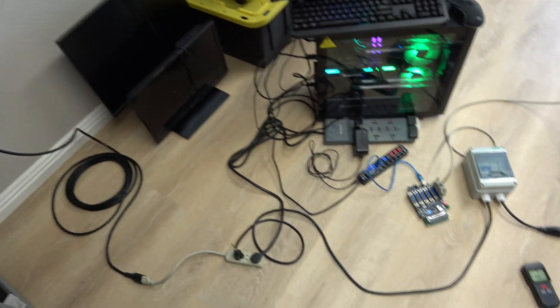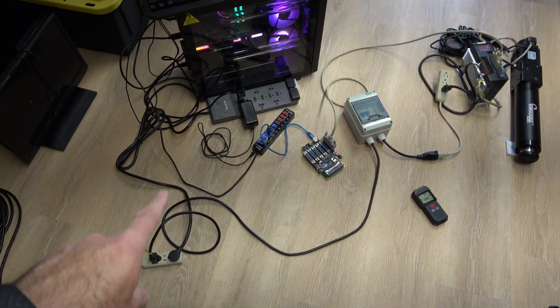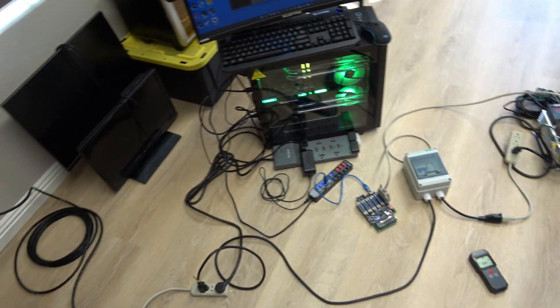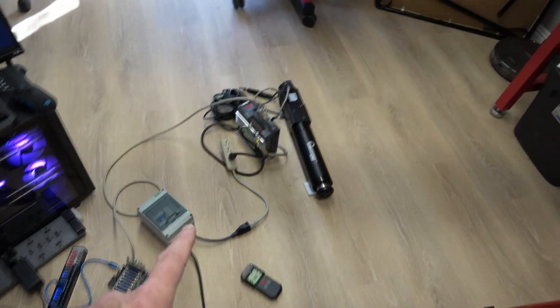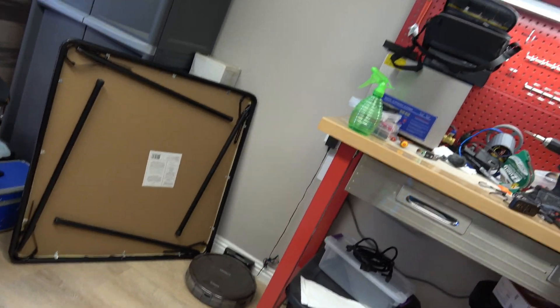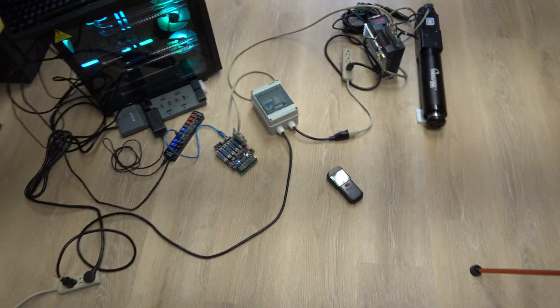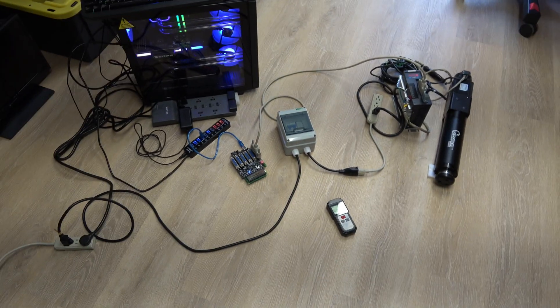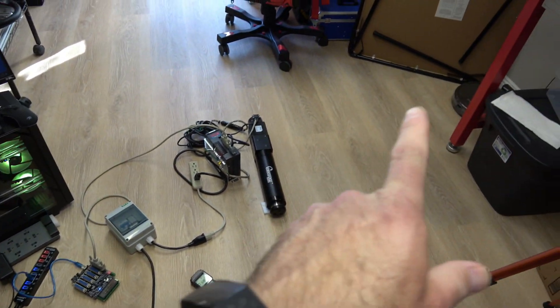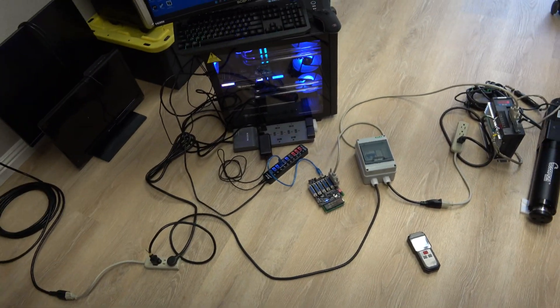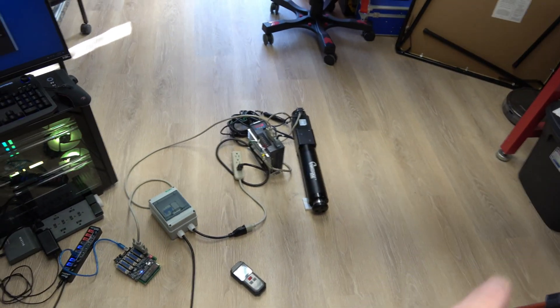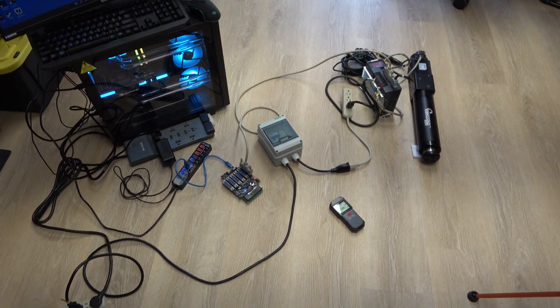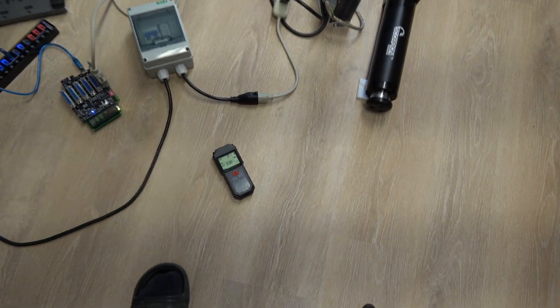So if you connect the PC on one outlet in one room, and then connect the servo on another outlet on another side of the room, you're going to have a ground loop the size of the room. Because all the electrical wiring probably ends up in the same point, but you're going to have the whole room creating a loop that will transmit too much noise.